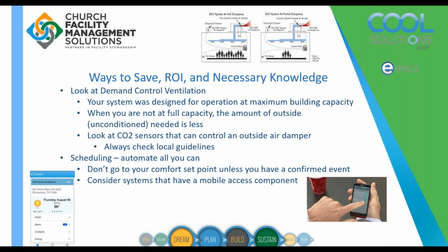So when we talk about demand control ventilation, your system was designed with max capacity in mind. That means it also was designed to have the most fresh air that would be required when you're fully occupied, to get the proper fresh air exchange and to make sure our CO2 levels don't go up too high. Most of us are not operating at full capacity day in, day out. Because of that, we can take a look at our demand control ventilation, our outside air, how much we're bringing in.